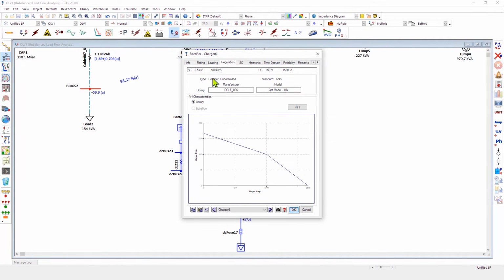ETAP includes a rectifier library where you can enter the manufacturer characteristics of the rectifier, such as its relationship of the voltage with respect to the output current. You can also define the rectifier as controlled or uncontrolled. This will allow some regulation on the rectifier input and output terminals depending upon the flow of power. In this case, we are using an uncontrolled rectifier, which implies that as the output current demand increases, the output voltage at the rectifier also starts reducing, and therefore it is an uncontrolled rectifier.